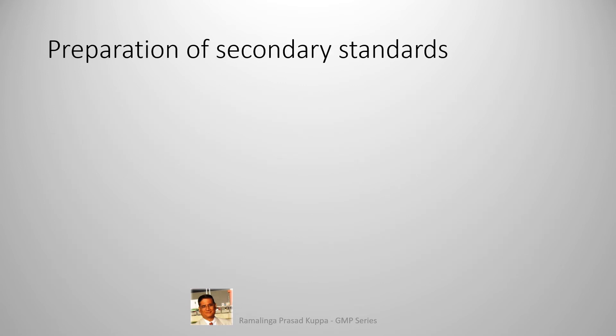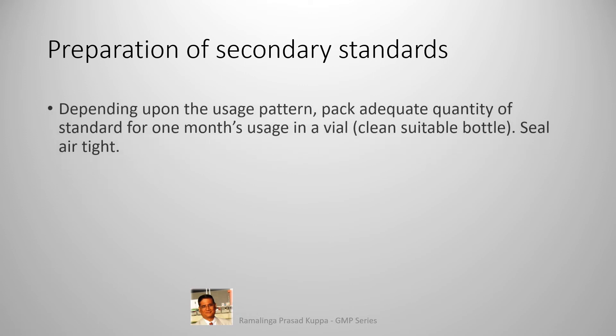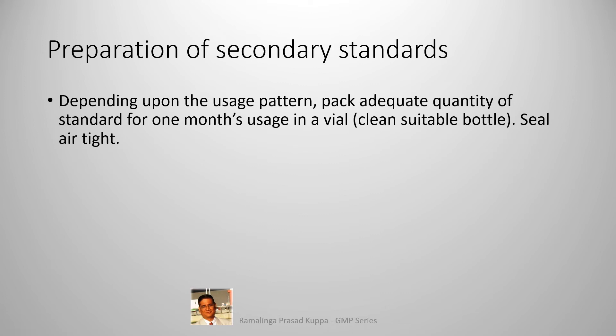For preparation of secondary standards, depending upon the usage pattern, pack an adequate quantity of standard for one month's usage into a clean, suitable bottle. Seal it airtight. If usage is more, larger quantities may be packed for each vial. Seal tightly to protect the standard from deterioration or degradation.